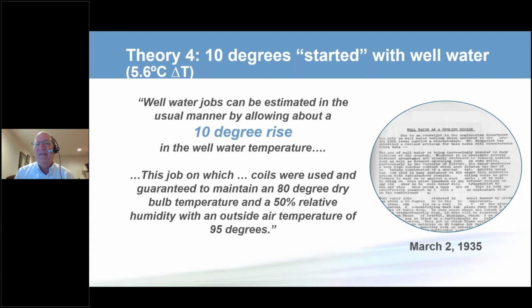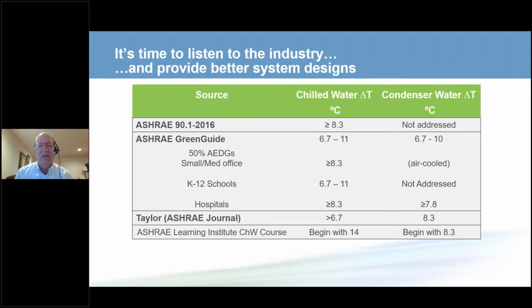So the 10 degree delta T, 10 degrees Fahrenheit, which is 5.6 degrees C delta T, we've been using that for at least 85 years. And the question today is, is that the proper delta T, using the technologies that we have today, in order to design our systems? When we look at what the industry is telling us, we should be using higher delta Ts and lower flow rates in our systems. And we'll talk about why, but first we want to talk about what the industry is saying.